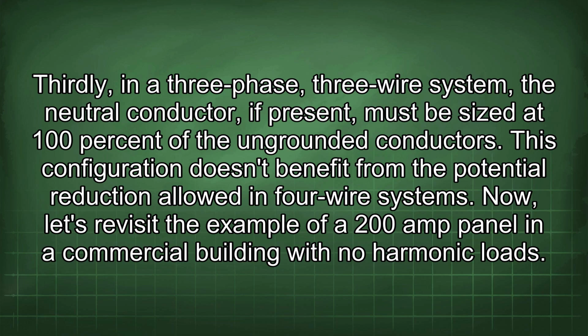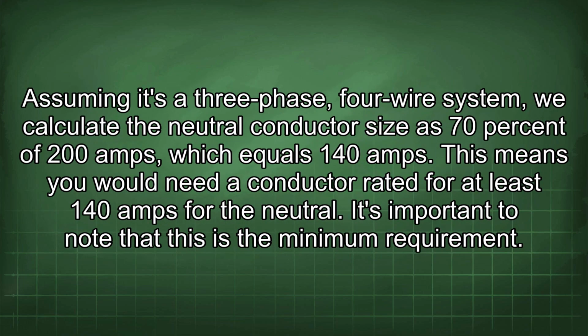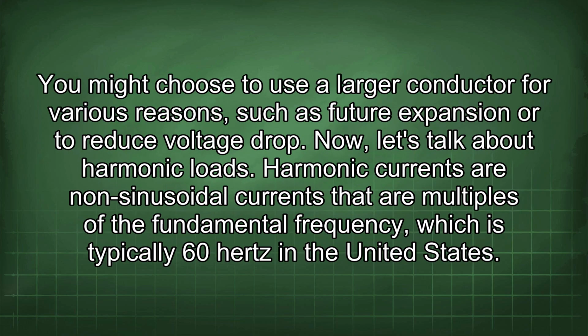Now, let's revisit the example of a 200 amp panel in a commercial building with no harmonic loads. Assuming it's a three-phase, four-wire system, we calculate the neutral conductor size as 70% of 200 amps, which equals 140 amps. This means you would need a conductor rated for at least 140 amps for the neutral. It's important to note that this is the minimum requirement. You might choose to use a larger conductor for various reasons, such as future expansion or to reduce voltage drop.